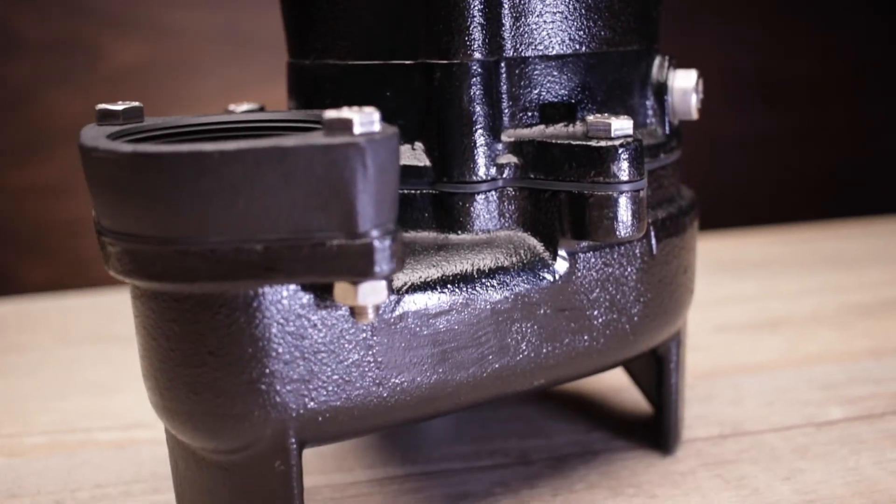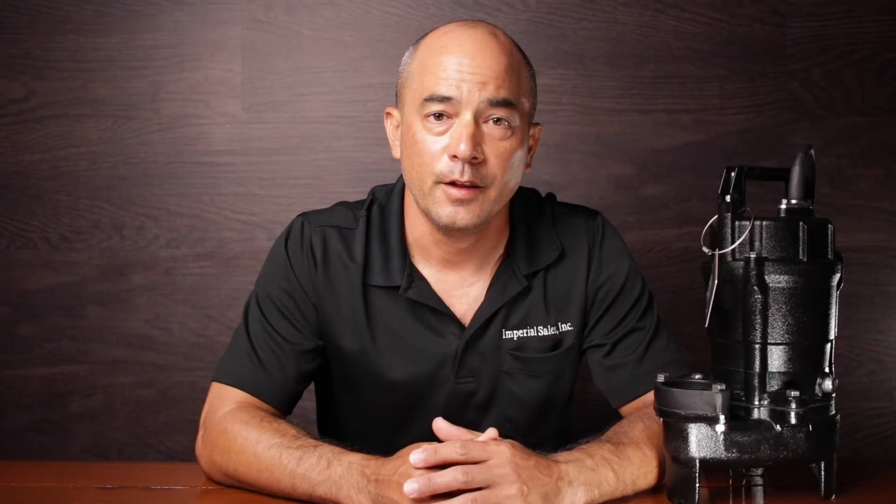It can pass solids up to an inch and 3 eighths or 35 millimeters. The 50 UT 2.4 S runs at peak efficiency pumping 40 gallons per minute at 18 feet of head.